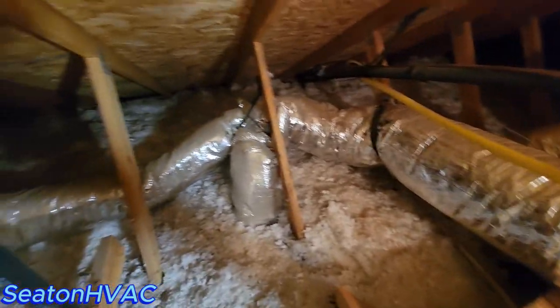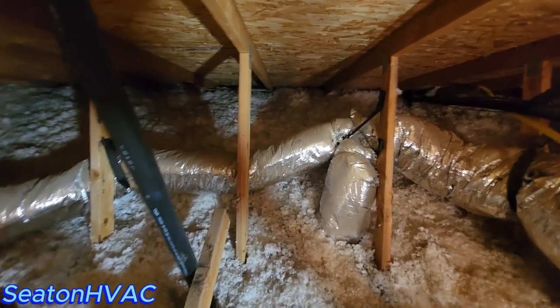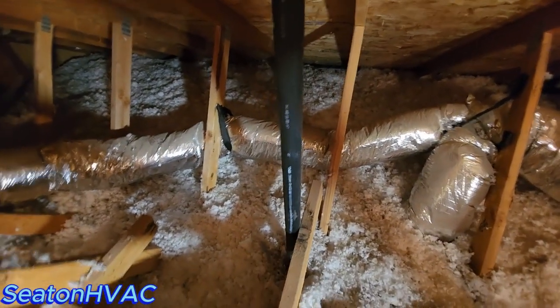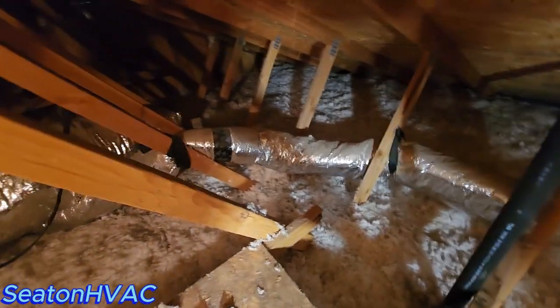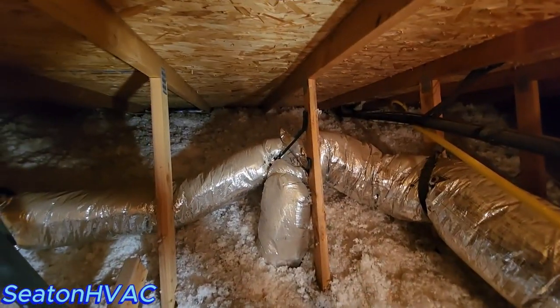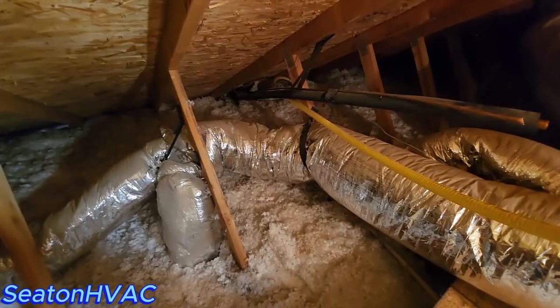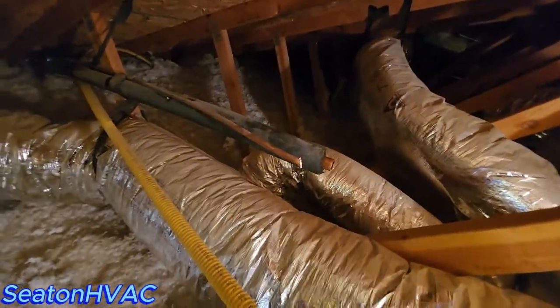I mean, it's not the worst ductwork I've ever seen, but that's why I hate HVAC, it's never installed properly. Look at that dip, kink, hard turn, a Y installed all strange, dip, kinked. But we're not redoing all that, that could be another time if the airflow still sucks.